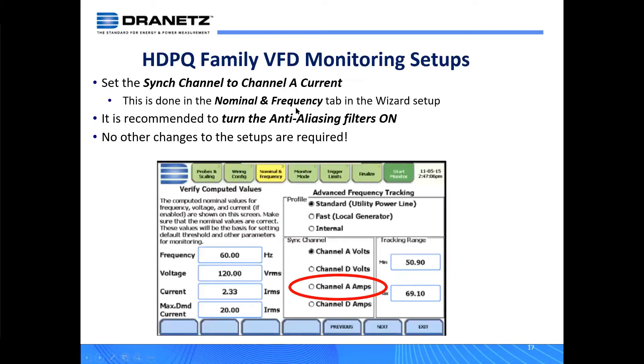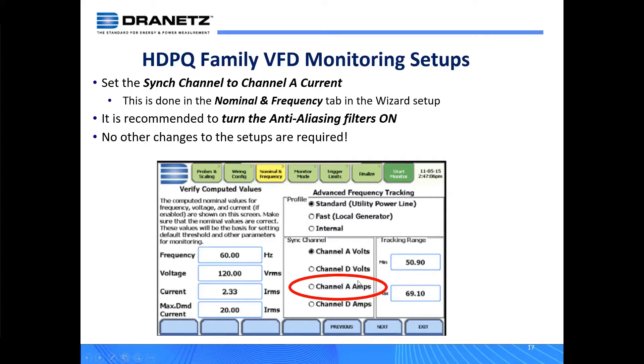For the HDPQ family, there's only two things you need to do. The first one is to set the sync channel to channel A current, as I mentioned. That's on this nominal and frequency tab. You could see right over here, sync channel is the A current. You could do the D current if you want, but the A current is typically right on that output of that VFD. If you have a single phase VFD or a three phase VFD, just choose channel A sync channel. And of course, as it implies, you have to be measuring current to do this.